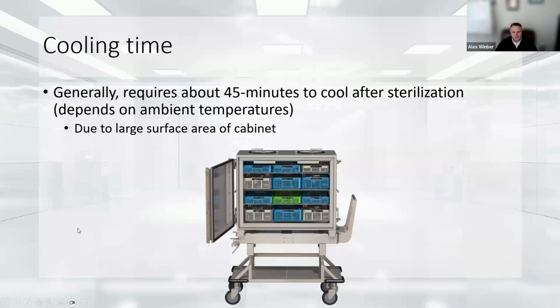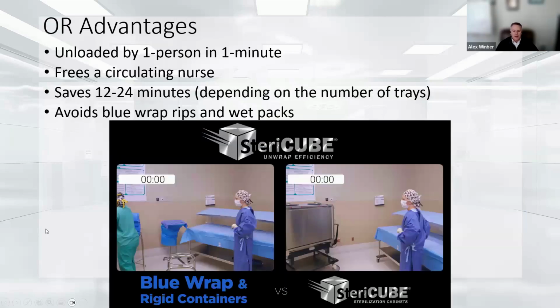All right, so with regard to cooling time, I mentioned before that you have to cool these rigid containers and blue wrap trays after sterilization. They cool them for 2 to 3 hours, and the reason they do that is to let all the moisture evaporate. Well, with SteriCUBE, because we have this funnel floor, we don't have a moisture issue. And also there's a lot of surface area with a SteriCUBE. It's a big box. So it takes about 45 minutes to cool versus 2 to 3 hours with standard instruments.